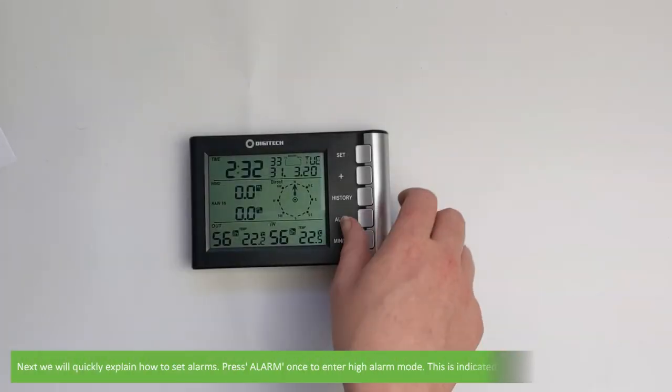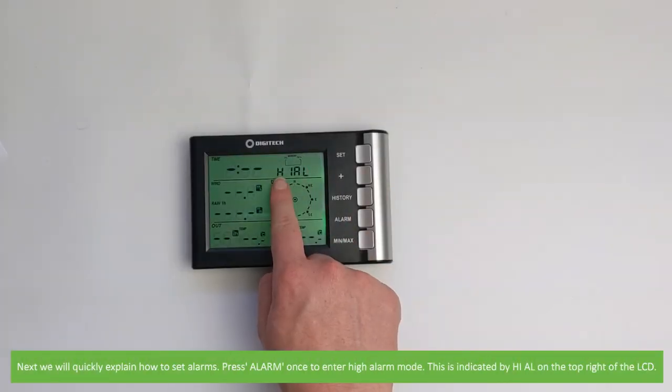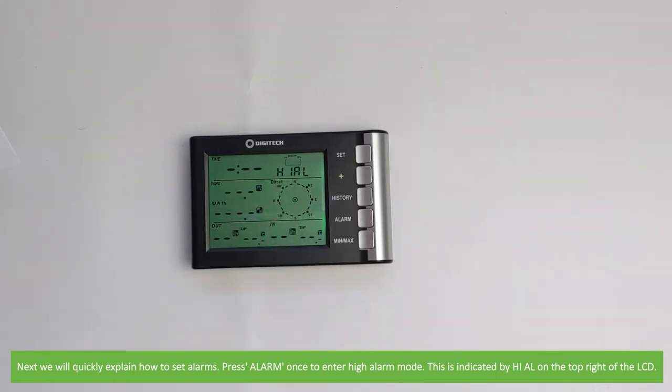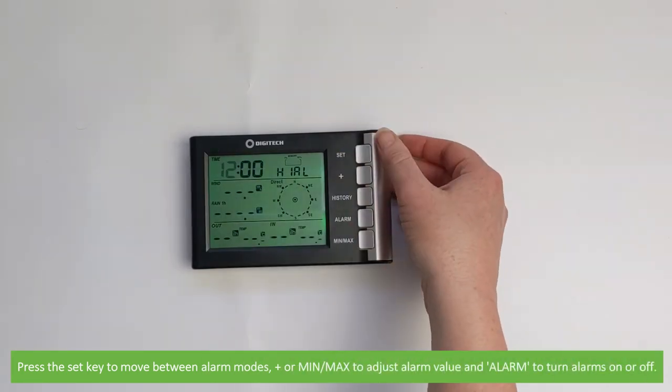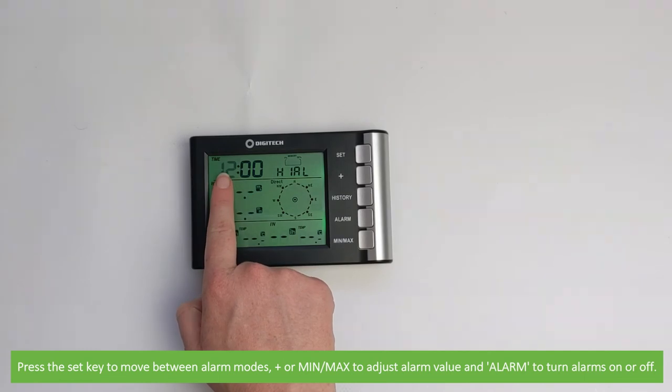Next we will quickly explain how to set alarms. Press alarm once to enter high alarm mode. This is indicated by H-I-A-L on the top right of the LCD. Press the set key to move between alarm modes, plus or min max to adjust alarm value and alarm to turn alarms on or off.